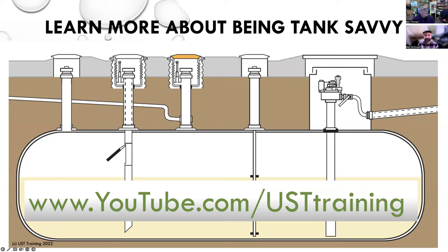Okay, good. Bill Combs asked whether tank gauges can find leaks in manifolded tanks. They normally have to be valved off to separate the two tanks so that the test will run properly. So if your tanks are manifolded, you want to make sure your tank gauge is certified for those manifoldings, or there is a physical or an electronic way to isolate those, because you can't test them together. They have to be separated, and each tank is measured separately.